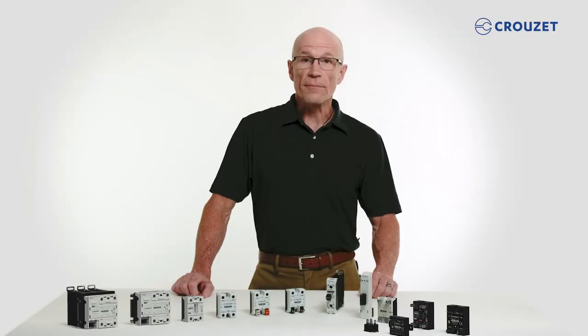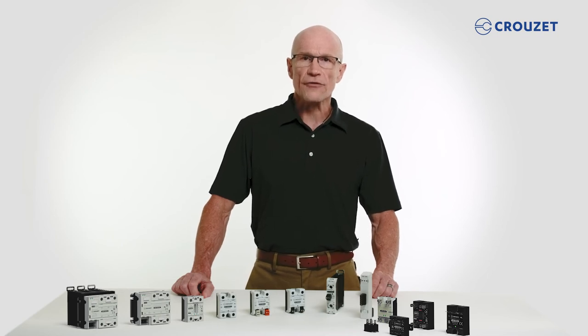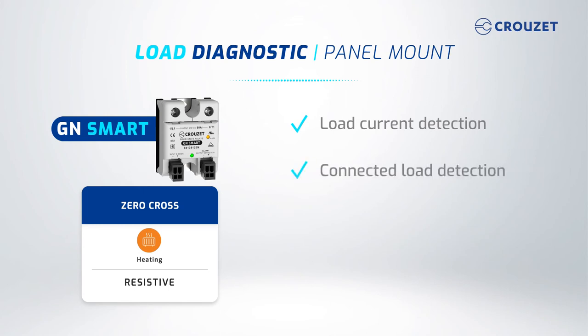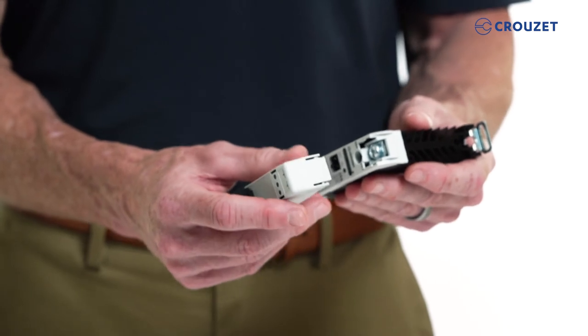Some uses, such as on plastic injection molding and thermoset machines, require more than just switching on and off, but also status feedback. Crouzet's GN Smart family of products is the right choice for these applications. The GN Smart panel mount SSR family provides an option that can detect if there is a load current, or a different option that informs whether a load is connected or not, whether the relay is open or closed, and the status of the fuse or circuit breaker. There is also a module that can be inserted in the GNR family of DIN rail SSRs to give a full status of the load.